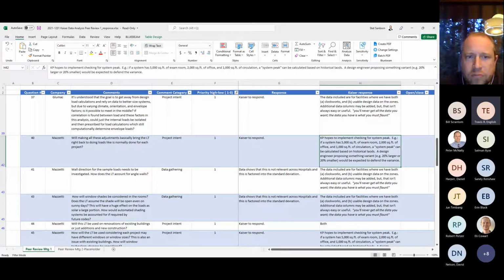Coming up this year, we're going to start to implement a change process where, say Bill, you would write the acceptance criteria for San Marcos: on a 70-degree day, this is how much those pumps are supposed to be running, this is how much those chillers are supposed to be running, this is how much the boilers and air handlers are supposed to be running. When we get into commissioning and we're at that 70-degree day, if it's radically off, then as the engineer of record you would need to reissue the acceptance criteria for the system with a reason—this is why it's different from my design. That's the process we're moving towards.